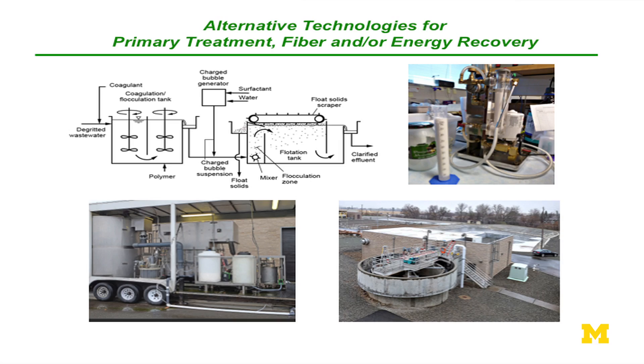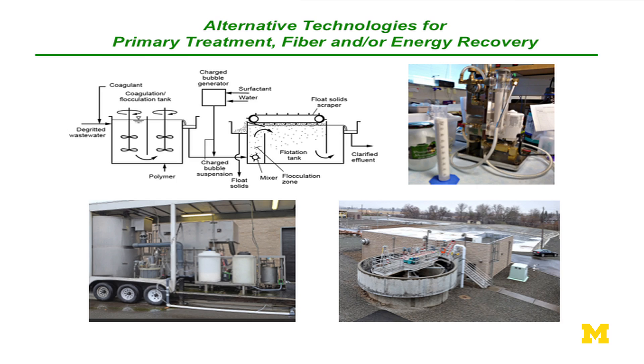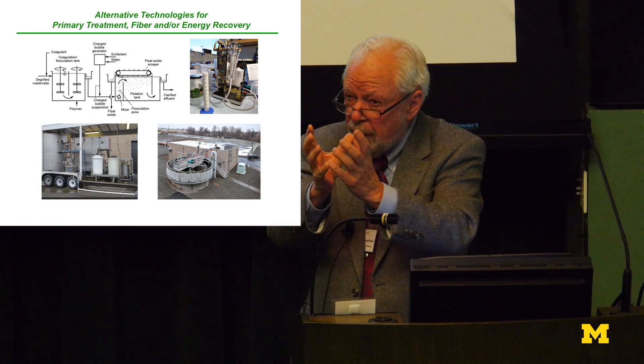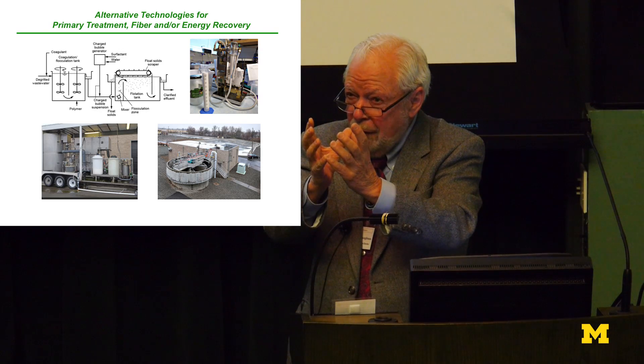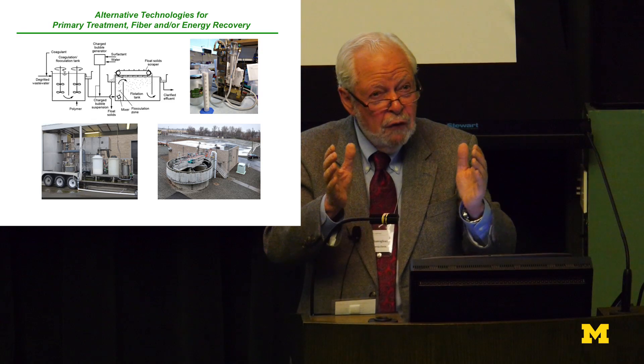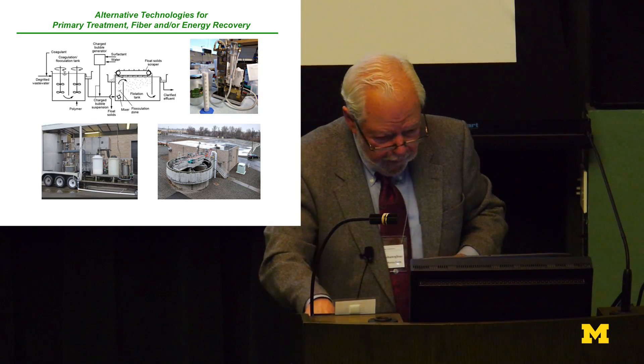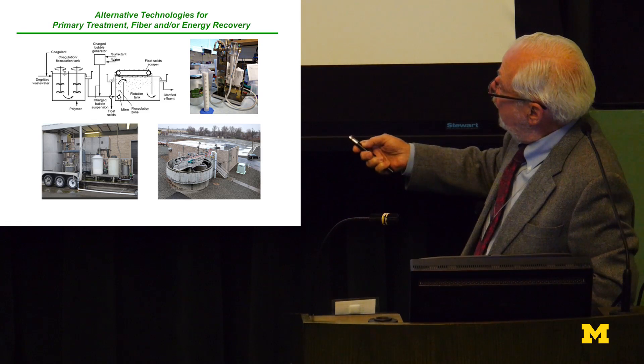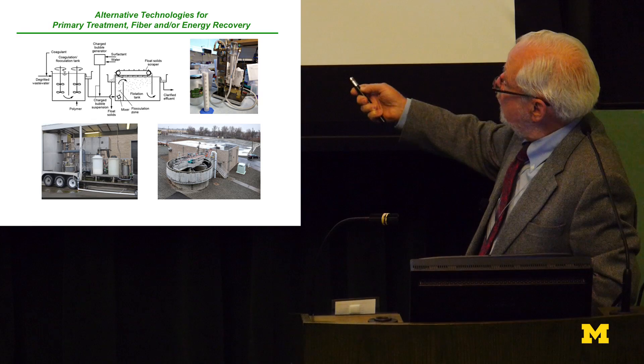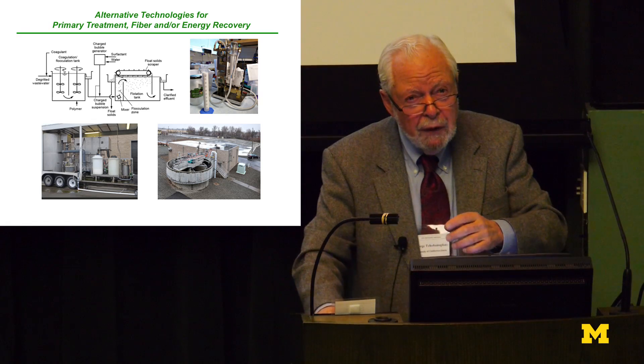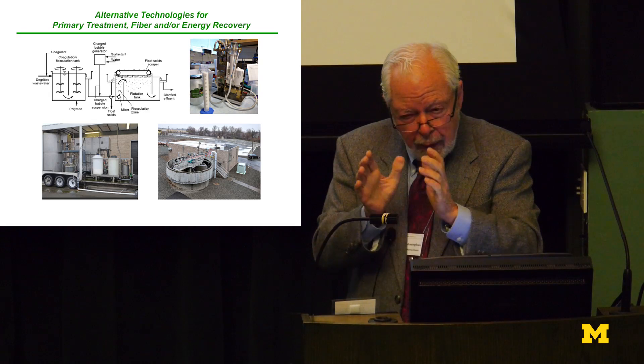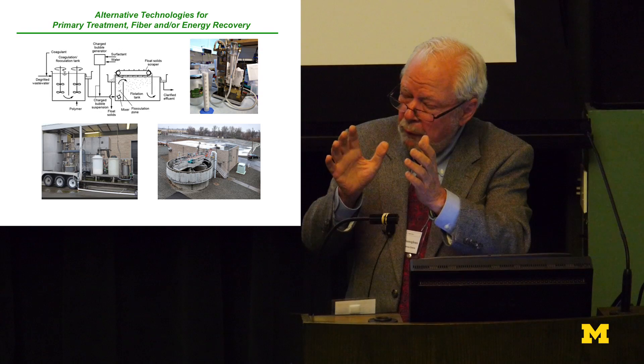The next idea is charged bubble flotation — very different from dissolved air flotation. You produce a froth and coat it with a polymer to which you can also add nanoparticles for the removal of specific constituents. The area required is about one-fifth that needed for conventional dissolved air flotation. This little test unit on the trailer will replace the large existing unit and will go right within the building. If there are specific compounds in the wastewater to remove, you can target the nanoparticles for them.